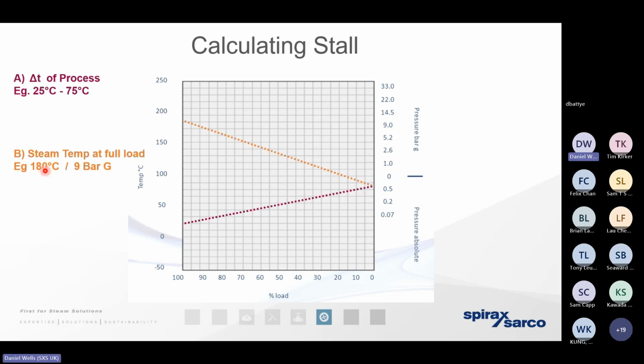The next thing we want to look at is the demand for steam. So at 100% load, where we need to heat the secondary side from 25 to 75, we may need steam at 180 degrees, 9 bar gauge. When we don't need to add any steam to the heat exchanger, the demand for steam is 0, so you can see the 2 points taper down.